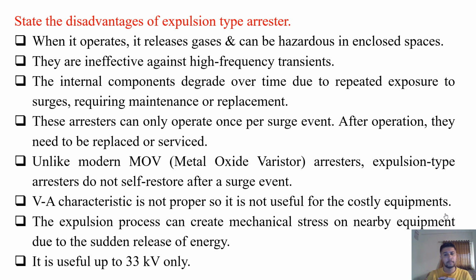Unlike modern MOV metal oxide varistors, expulsion type arrestors do not self-restore after a surge event. The voltage current characteristic is not proper for this type of arrestor, so it is not useful for costly equipment. The expulsion process can create mechanical stress on nearby equipment due to the sudden release of energy. It is useful up to a 33 kilovolt system, the medium voltage distribution system. So these are several disadvantages of the expulsion type arrestor.